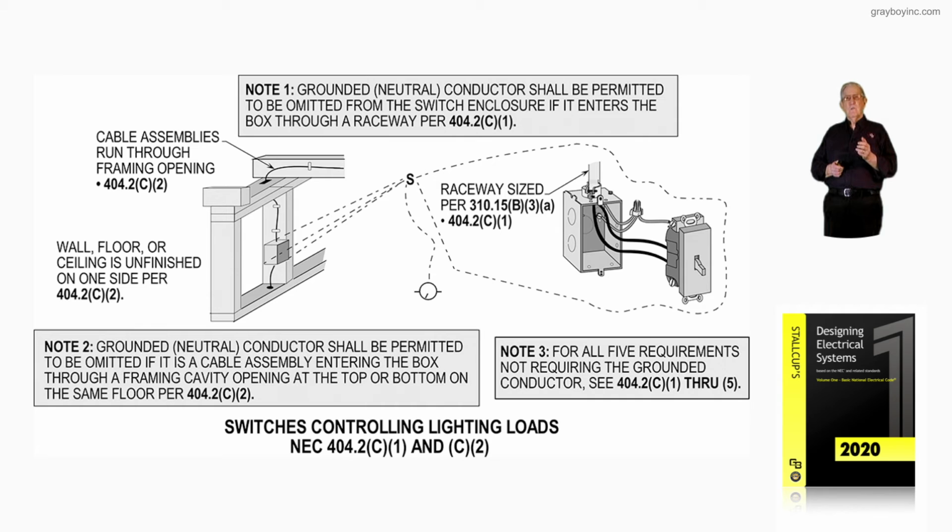And if you look at the raceway size, notice if the conduit is large enough to pull the neutral in later, then I would not have to pull that in accordance with 404.2(C)(1). And we do not have more than 3 current carrying conductors, so table 310.15(C)(1) would not be applicable.